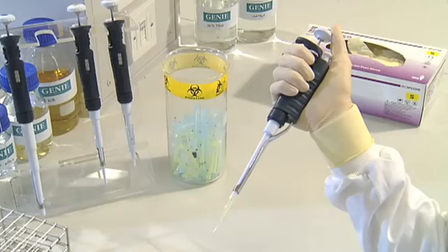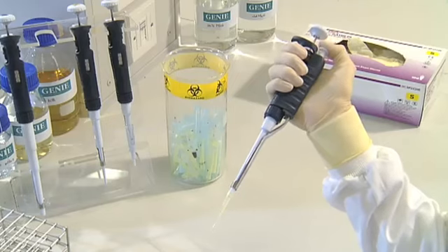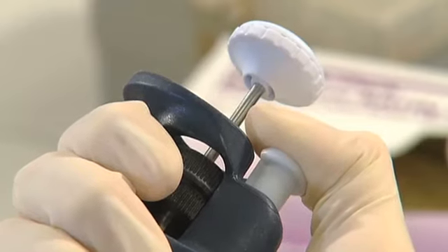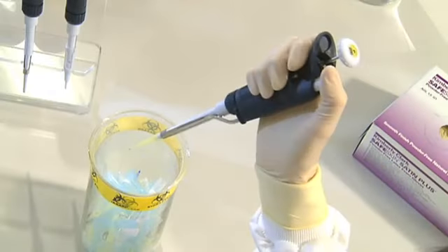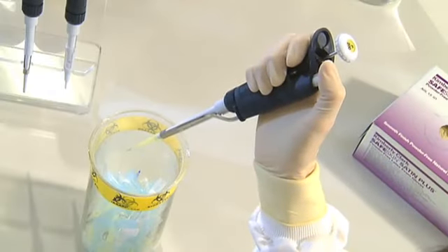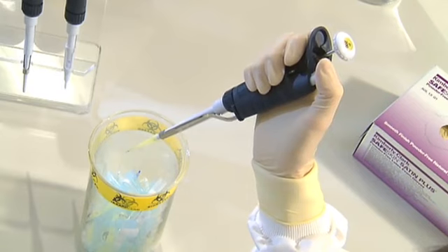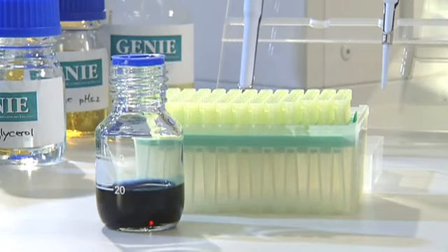Once you've dispensed the liquid, release the pipette tip from the pipette by pressing down on the tip ejector. This is the small white button at the top of the main body of the pipette. Be sure that the attached pipette tip is inside the appropriate waste container before pressing the tip ejector. A new clean pipette tip should be used with each new liquid, or if the tip touches any surface or any liquid other than the one you're pipetting. If in doubt, change the tip.